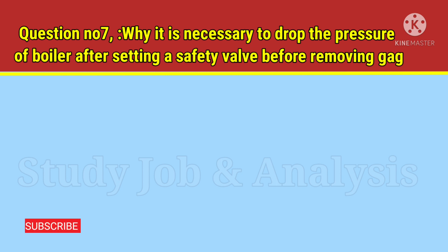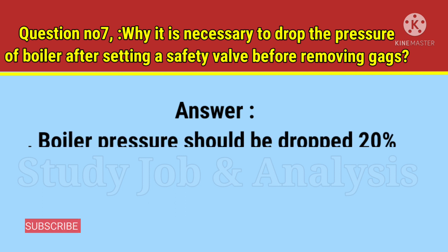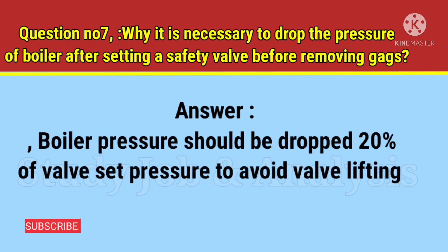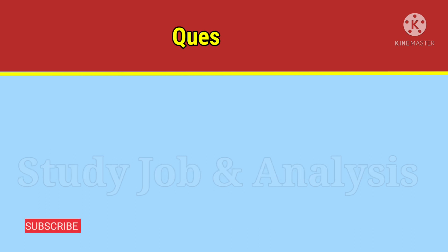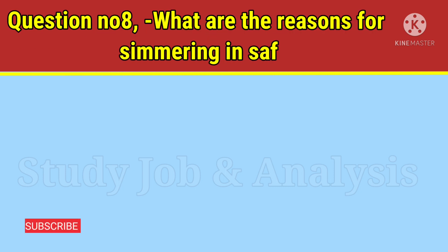Question number seven: why is it necessary to drop the pressure of the boiler after setting a safety valve, before removing gags? Answer: Boiler pressure should be dropped by 20 percent of the valve set pressure to avoid the valve lifting prematurely.